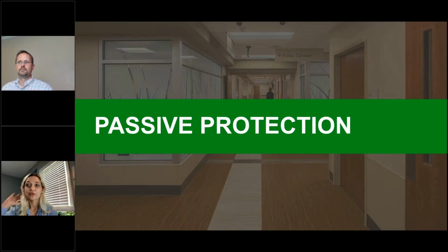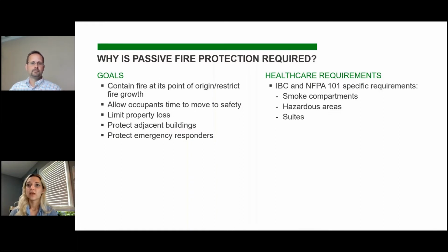Passive protection in general is going to be the rated construction that we see throughout buildings, and we're going to look at it really generally, and then we'll get more specific into each assembly. So in general, why is it required? Ultimately, our goal is to keep the fire wherever it started so it doesn't spread throughout the building. This allows occupants to egress safely and quickly, limits property loss, and ultimately protects the contents of the building, the contents of adjacent buildings if you have exterior rated walls, and then also protecting emergency responders to ensure that the building stays sturdy and standing while they're trying to do their job.